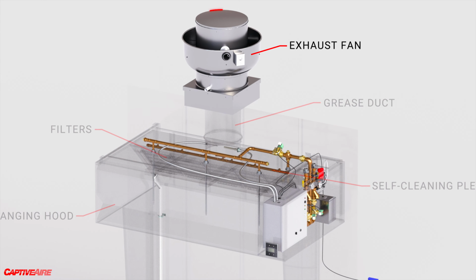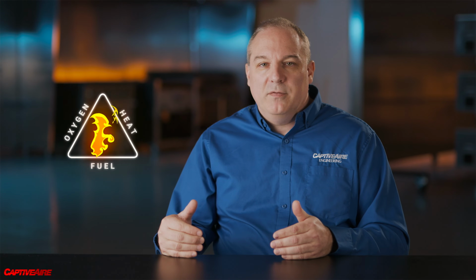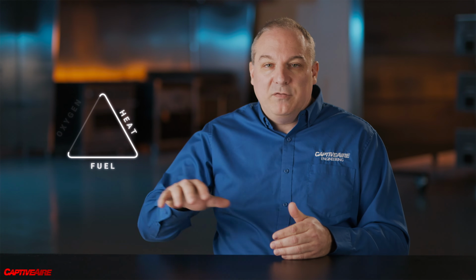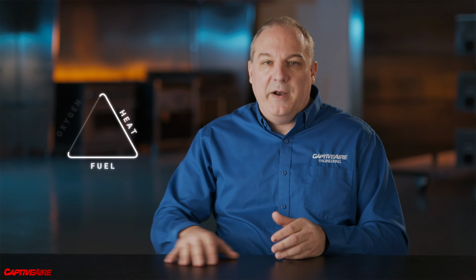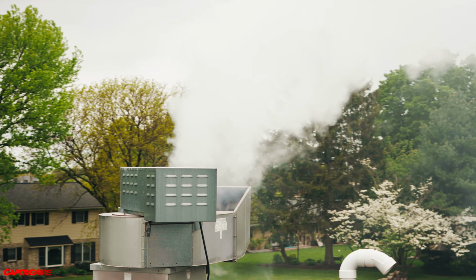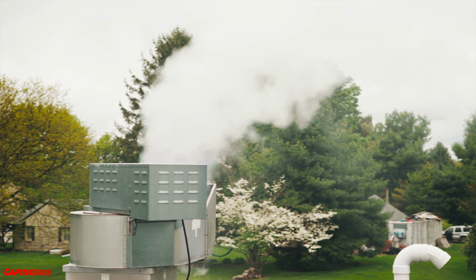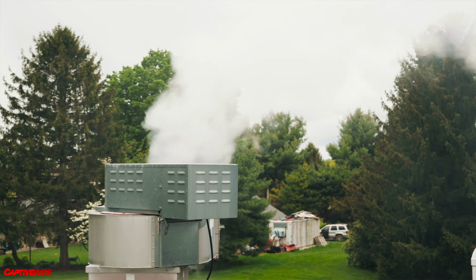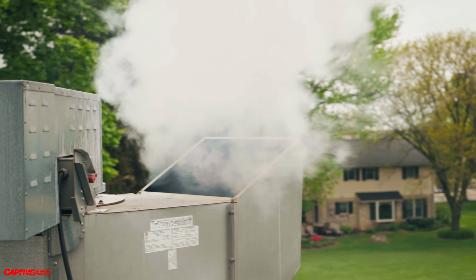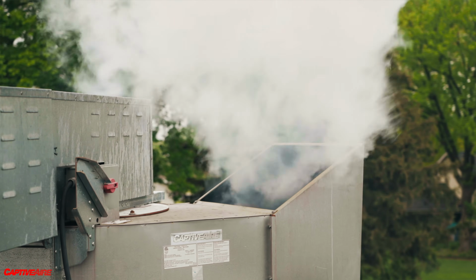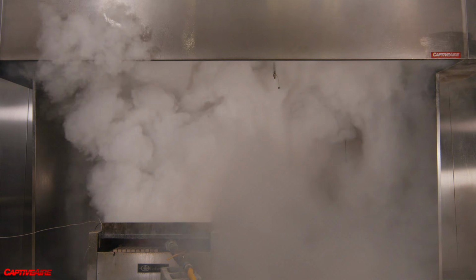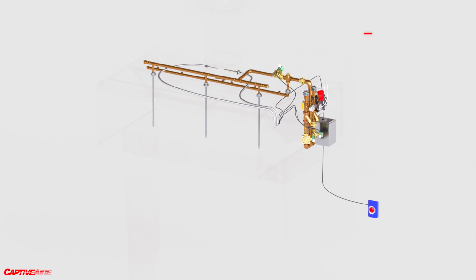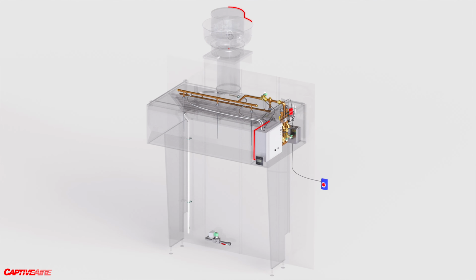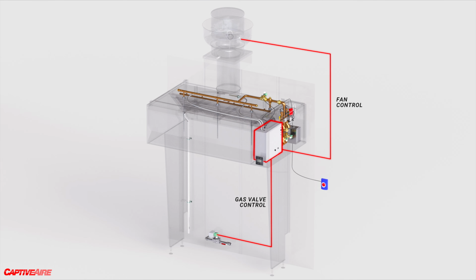There's several things that happen with a fire that relate to airflow. First of all, you want to do everything you can to suppress the amount of combustion air coming into the building. That's why code mandates that makeup air shut off in a fire. We also want to turn the exhaust fan on to evacuate smoke. One of the major damages of fire is smoke damage in a building. So if we can keep the exhaust fan running with proper exhaust fan design, we can evacuate that smoke out of a building and help evacuate a lot of the damage out of the building. Fire suppression systems on their own do not do this. They have to be integrated into a larger system, and our controls handle all that.